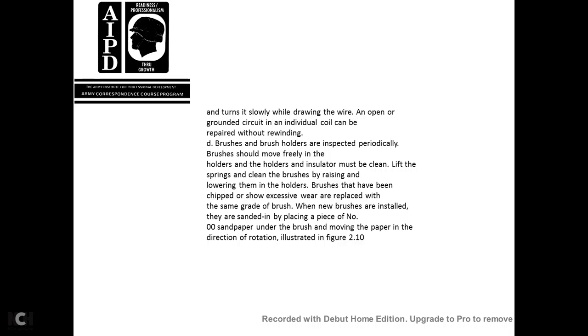An open or grounded circuit in an individual coil will be repaired without rewinding. Brushes and brush holders are inspected periodically. Brushes should move freely, and the holder insulators must be clean. Lift the springs and clean the brushes by raising and lowering them in the holders. Brushes that are chipped or excessively worn will be replaced with the same grade of brush.